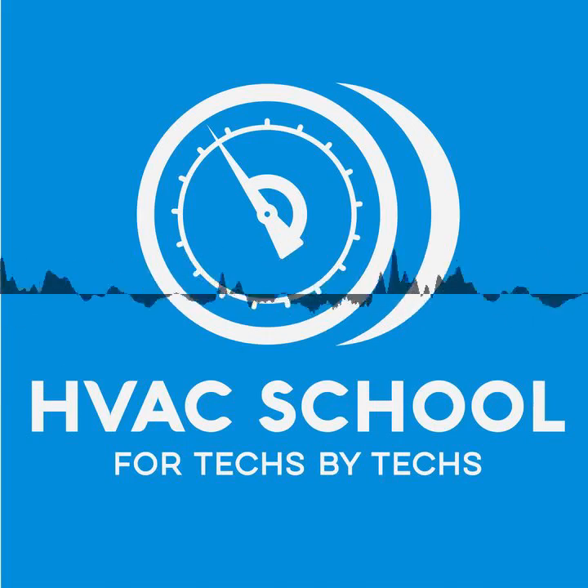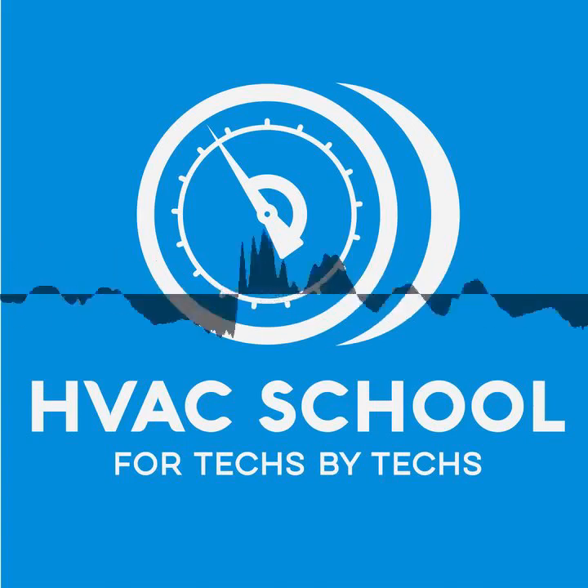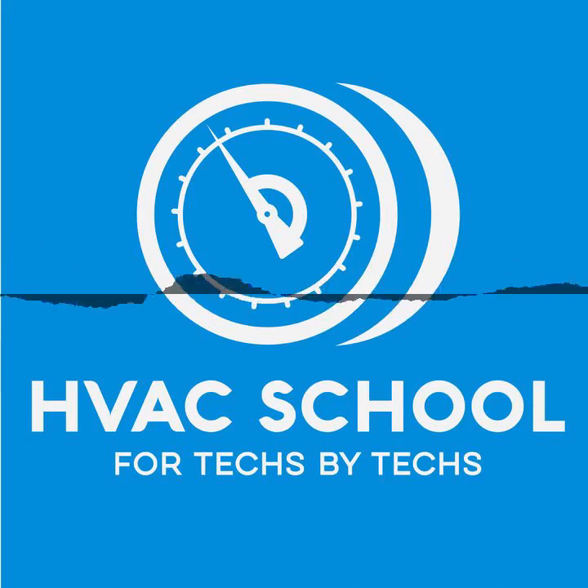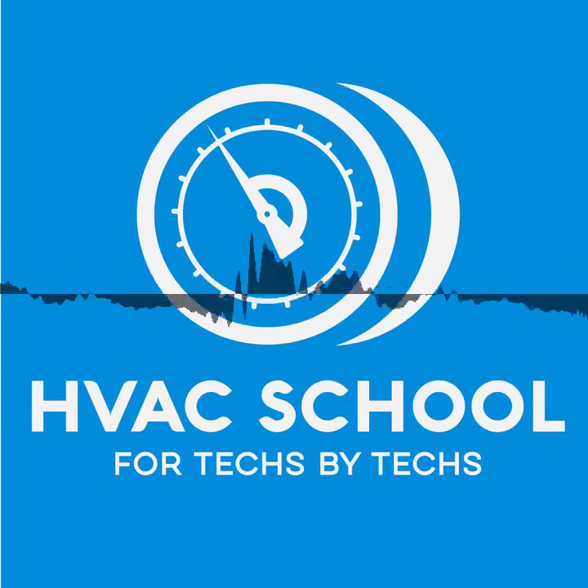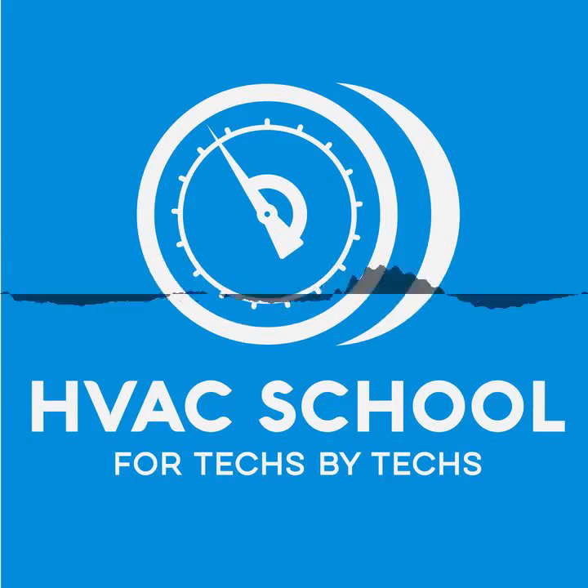And I really like it, it's a product we use at Kalos, at my business, in those applications. It's not the sort of thing that takes the place of other protocols, making sure you're following all the proper procedures: testing for acid, suction dryer, liquid line dryer, properly sized dryers, removing them from service once all the acid is taken care of. There are all these steps you have to take, but in some cases, using this product can help you get to where you have no acid in the system.